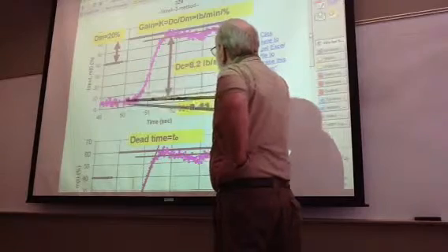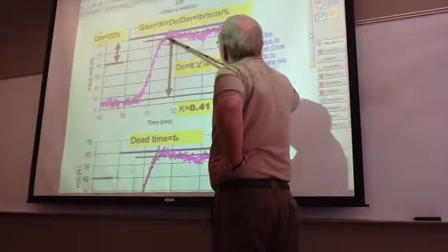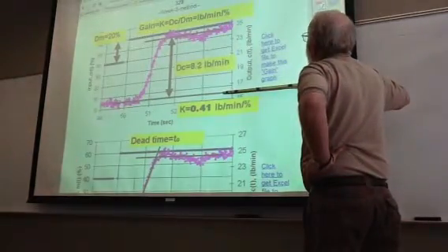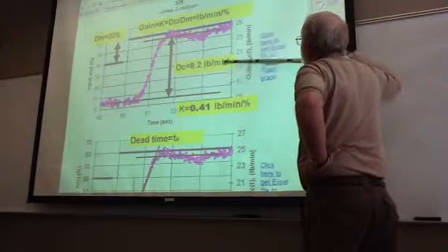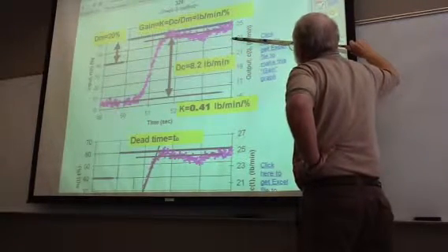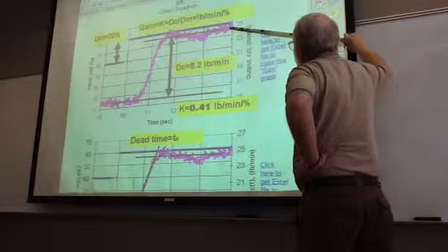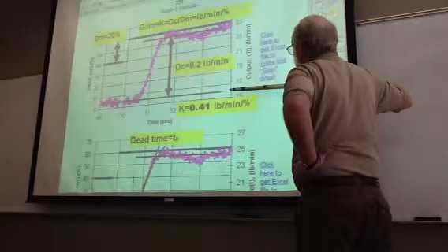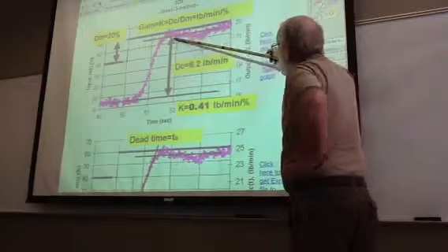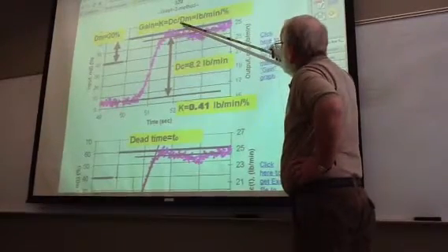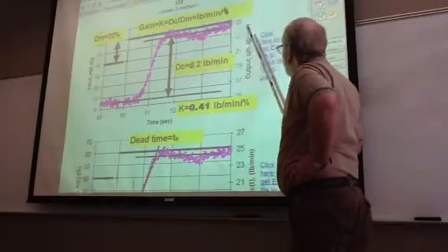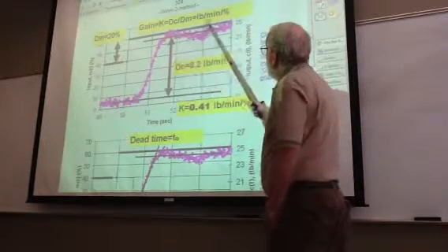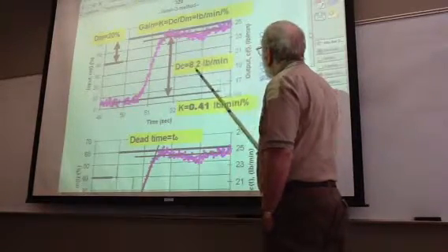Then here's the purple or pink curve, which is the output curve over here. It starts around 16 pounds per minute. This must be flow. And it goes up to 24 and a half. This says 8.2, so this must be a little above, whatever. So this delta here is the delta of the output. C is the output, this is C over here, and this is M over here. Delta of the output is 8.2 pounds per minute.